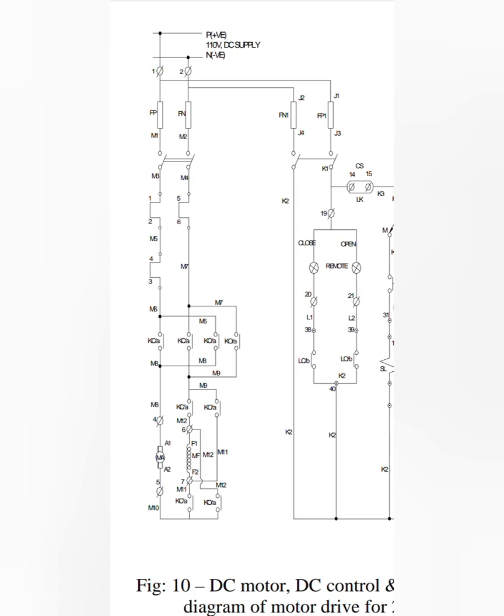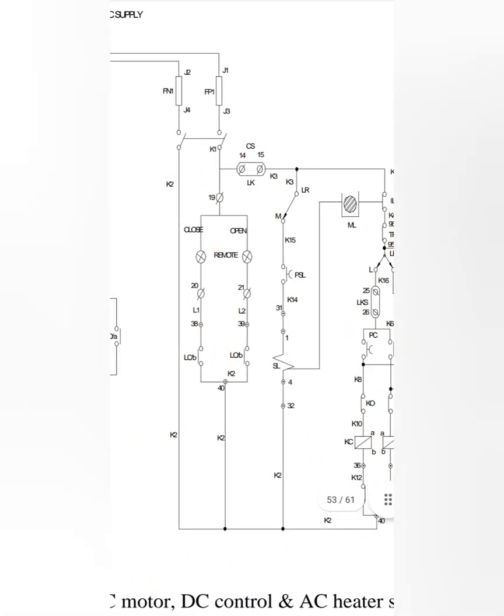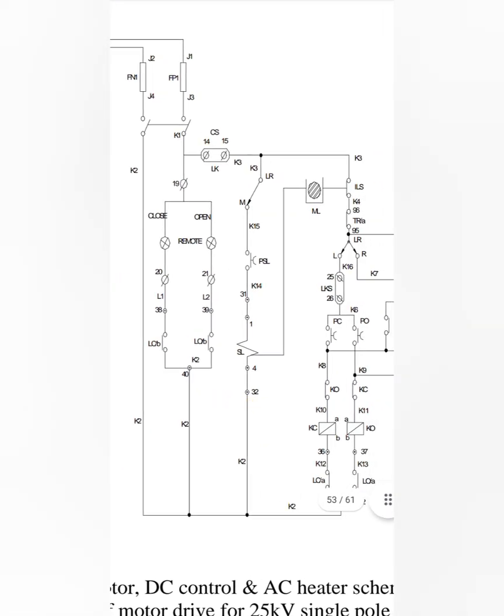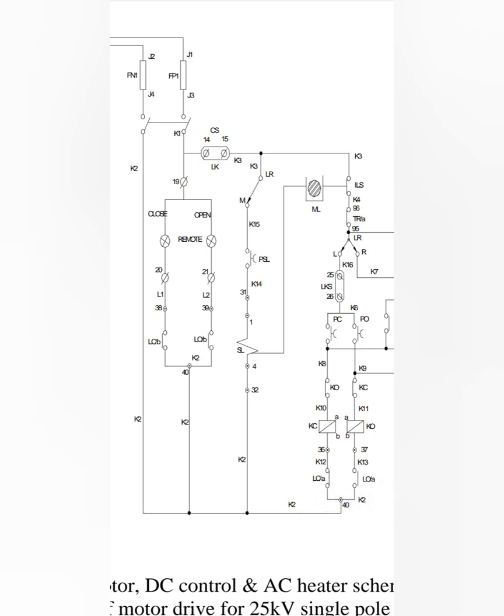For controlling, then the local and the remote — for that we have a separate fuse for control supplies, that is your fuse FP1, then further it will move to your control supply. This is your local and remote switch. Here LR is mentioned, so now we are going to see L which means your local operations. For local operation, as I said, it will be carried out by your push button — we need to manually push that push button, and then after pushing that, NO and NC will be made and then it will further move to your supply.